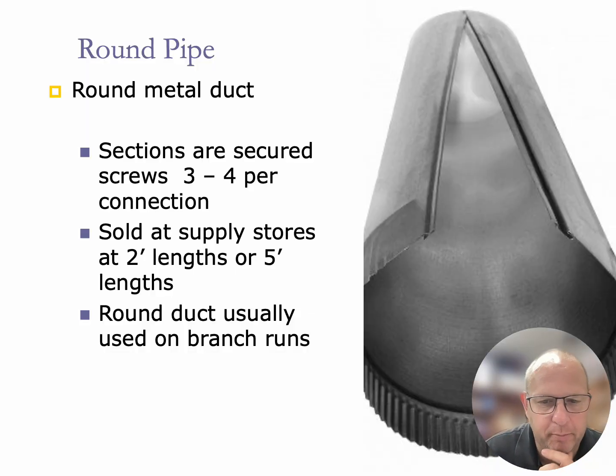So when we're looking at metal pipe that's running from the main trunk out of the takeoff and then going to the area in which we're going to be attaching it to a boot and then to a register to go into a room, those sections of pipe happen to be from 2 feet long to 5 feet in length. The sections are put together by putting 3 to 4 screws within the ductwork, and there are specific positions that you want to put those screws.